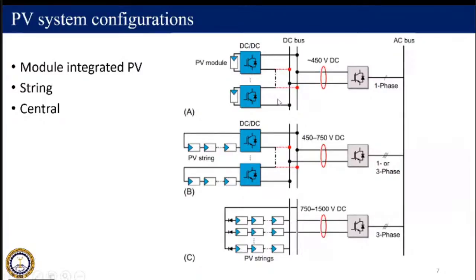Then we have a string inverter, where instead of having a converter for each single module, many PVs will be connected in a string, and that will be given to a DC-DC converter. Then again we have an inverter, either single phase or three phase, because with many PVs such a large power cannot be injected into the single phase grid, so we may have to go for three phase. The DC bus voltage here can go up to 750 because we have many PVs connected in series, so the voltage will be higher.